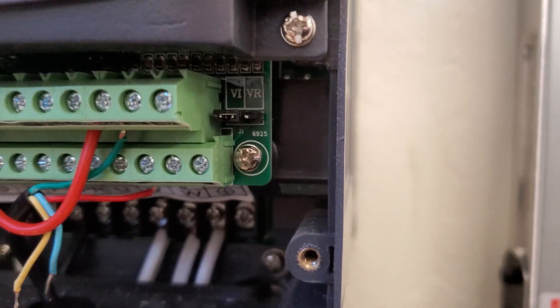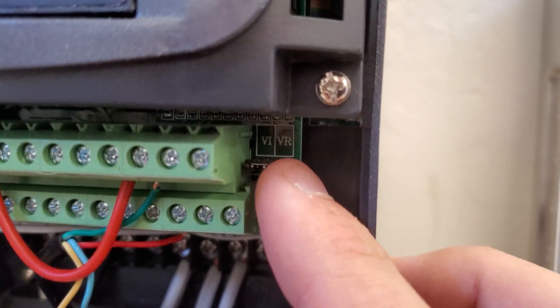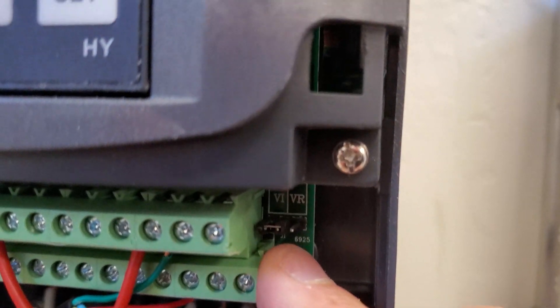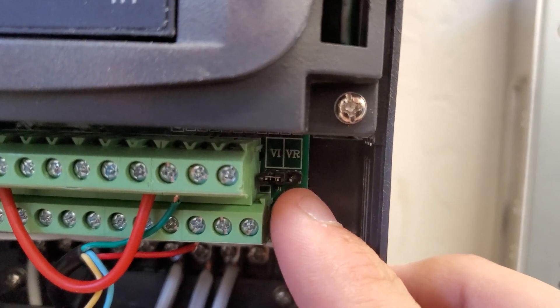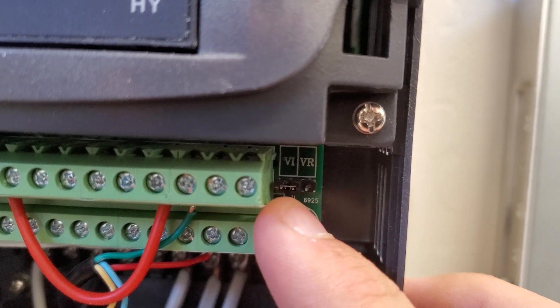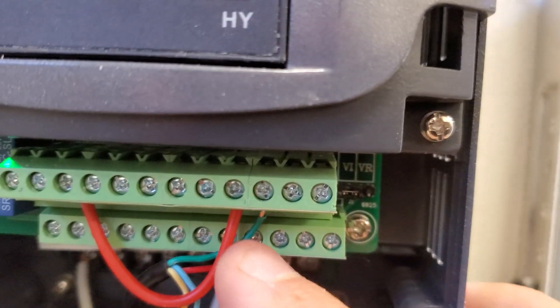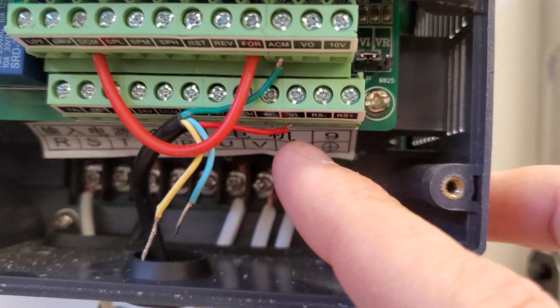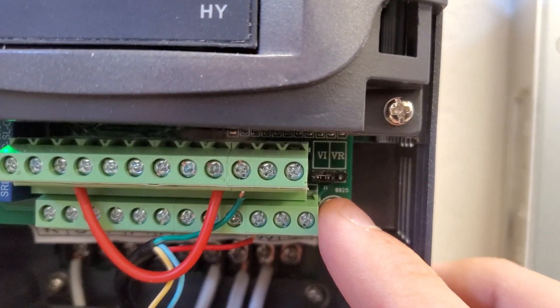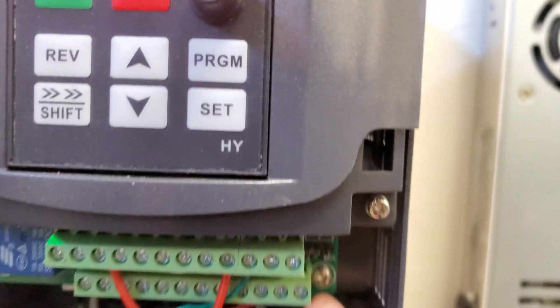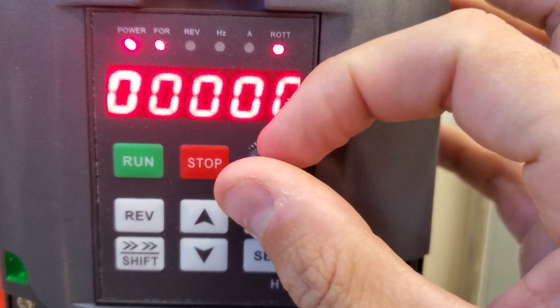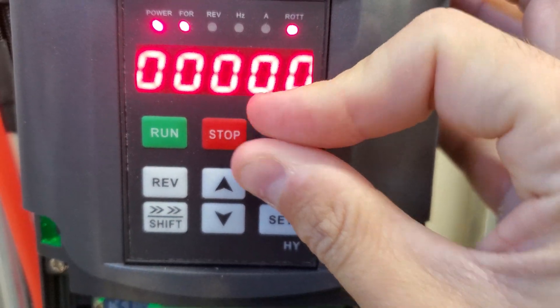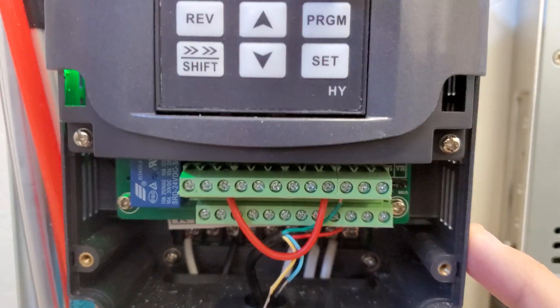This is a big step that I only found on one tutorial that seemed to do the trick is this little jumper right here. It's by default set on the right under VR. You need to pull that and set it to the left under VI. If you don't do that, it will not accept any information coming in from this VI terminal here. So you have to do that. Make sure you do that when you do your wiring. Do it while it's turned off. What that does is it disables this little knob here, and accepts the signal from this. So make sure you do that.